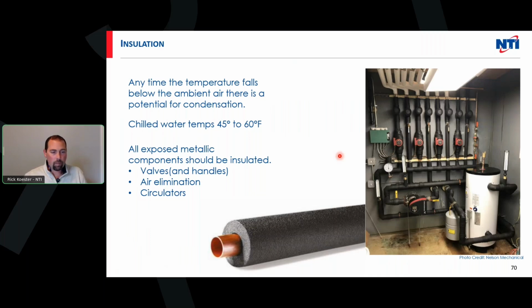So having the proper insulation matters, and this is something I saw Nelson do. I believe he's in the States. This was a job he actually went back to as a contractor to re-insulate somebody else's project because they didn't do it properly. So it's something we just have to be mindful of, not just because of the sweating, but because we want to make sure that every single one of those BTUs we're creating is getting in and transferring into the space as best as possible.